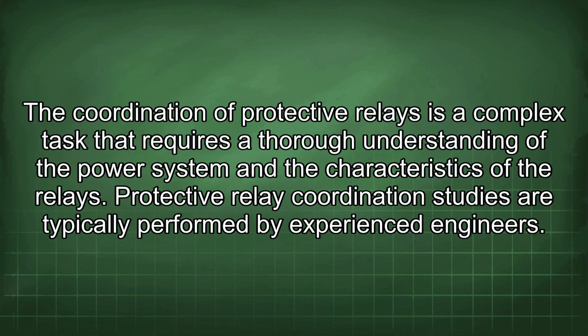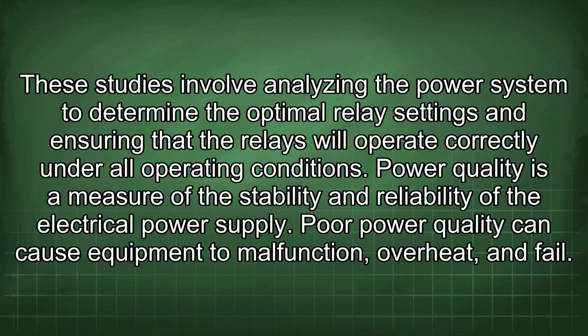The coordination of protective relays is a complex task that requires a thorough understanding of the power system and the characteristics of the relays. Protective relay coordination studies are typically performed by experienced engineers. These studies involve analyzing the power system to determine the optimal relay settings and ensuring that the relays will operate correctly under all operating conditions.